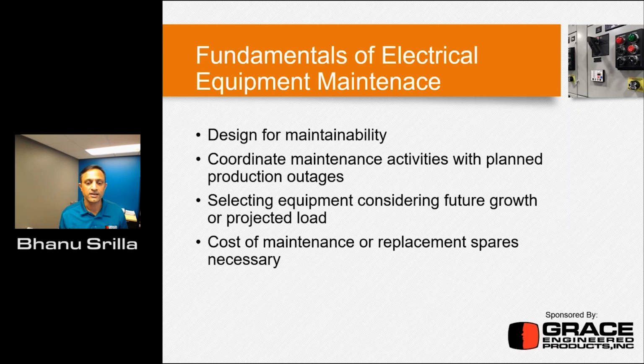So, selecting equipment considering future growth. These are all the things that I refer to as design criteria before you're designing equipment for a facility. You foresee in the next 5 or 6 years how the projected load is going to change, and you can design the equipment so you don't need to change it in that given 3 years or 2 years' time. So always make sure that you have future growth capabilities built into your equipment. For example, you require 3000 amps, for example, complete full load, right?